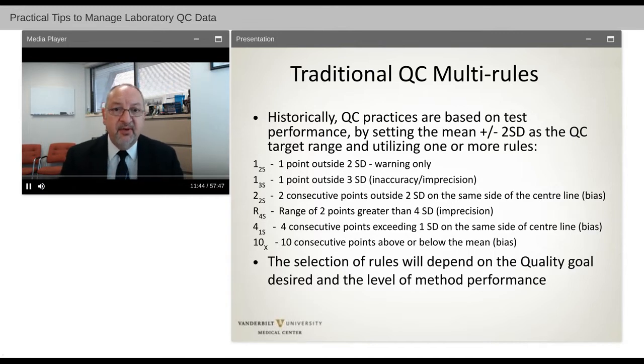And we can apply other types of rules, such as 2-2S, 4-1S, where 4 consecutive points exceed 1 standard deviation, or even 10 consecutive points on one side of the mean. The selection of rules that a laboratory uses depends on your quality goals and the tolerance you have for troubleshooting. If you set them too tight, you will overcall many, many failures and be troubleshooting the method more than you need to. In other words, false alarms. If you set the ranges too wide, the method will not be sensitive to picking up big shifts or trends that could affect patient results. So you want just that right range.